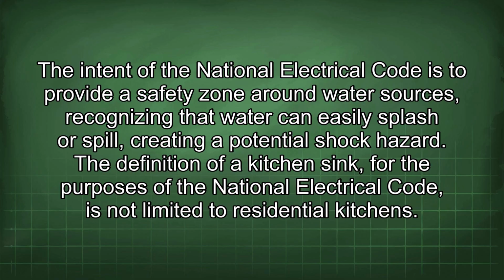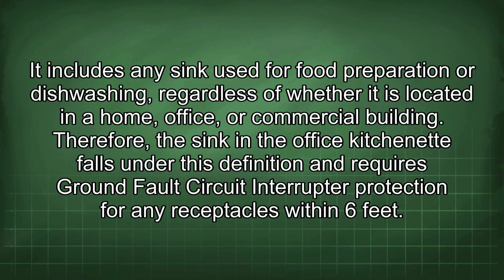The definition of a kitchen sink for the purposes of the National Electrical Code is not limited to residential kitchens. It includes any sink used for food preparation or dishwashing, regardless of whether it is located in a home, office, or commercial building. Therefore, the sink in the office kitchenette falls under this definition and requires ground fault circuit interrupter protection for any receptacles within 6 feet.